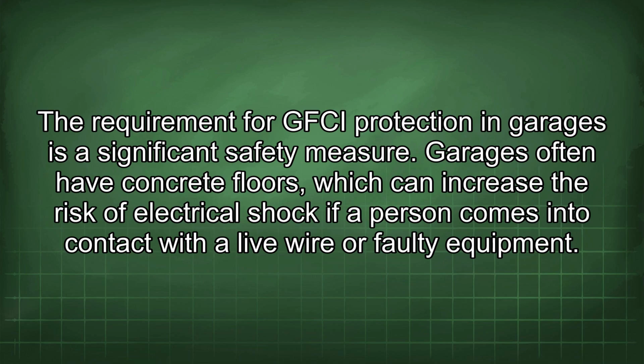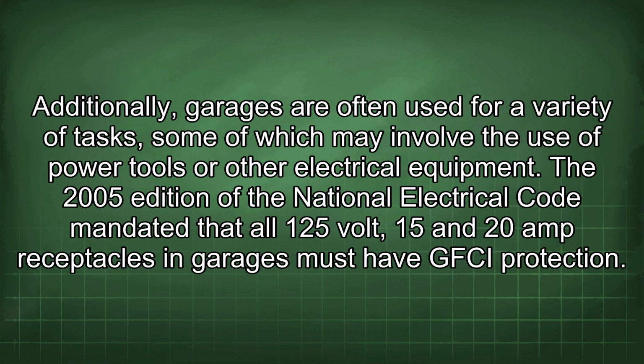The requirement for GFCI protection in garages is a significant safety measure. Garages often have concrete floors, which can increase the risk of electrical shock if a person comes into contact with a live wire or faulty equipment. Additionally, garages are often used for a variety of tasks, some of which may involve the use of power tools or other electrical equipment. The 2005 edition of the National Electrical Code mandated that all 125-volt, 15 and 20 amp receptacles in garages must have GFCI protection.